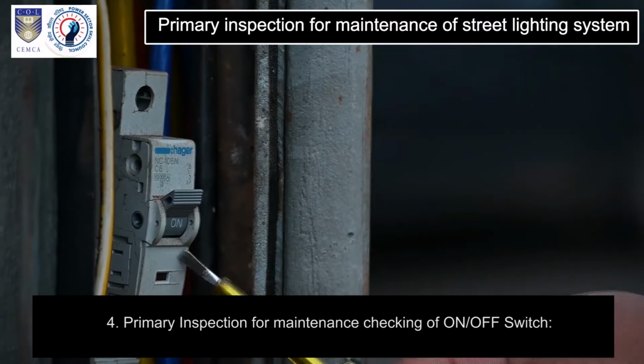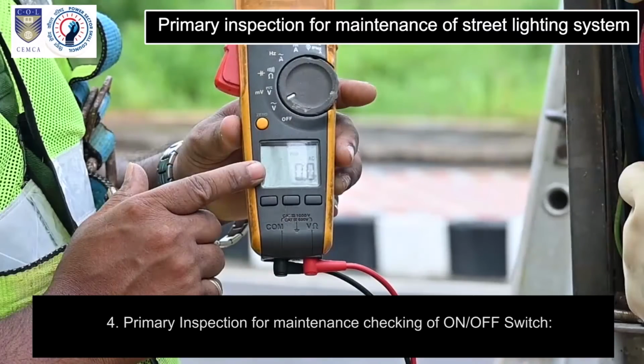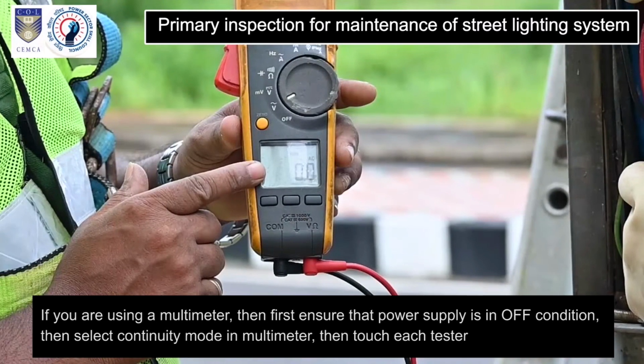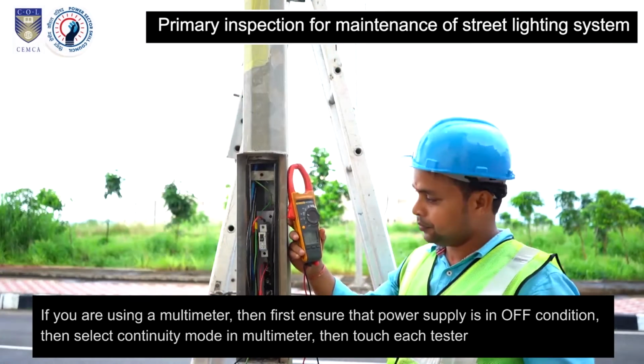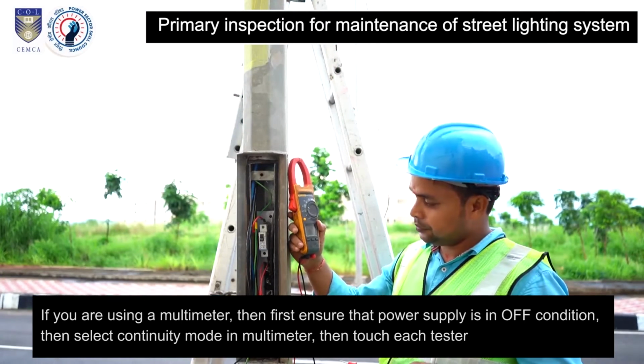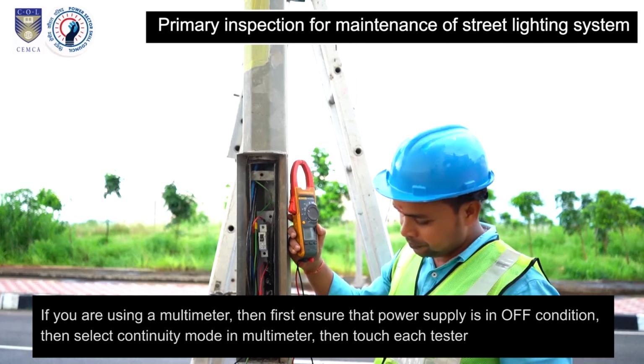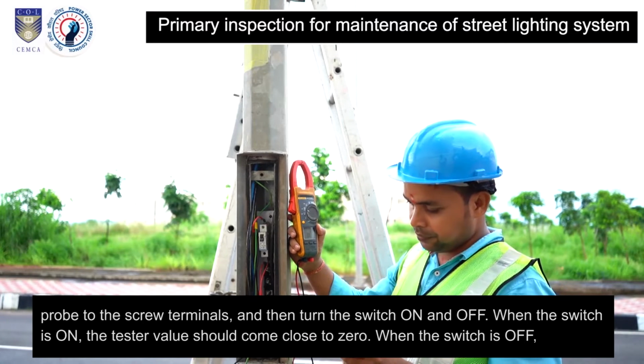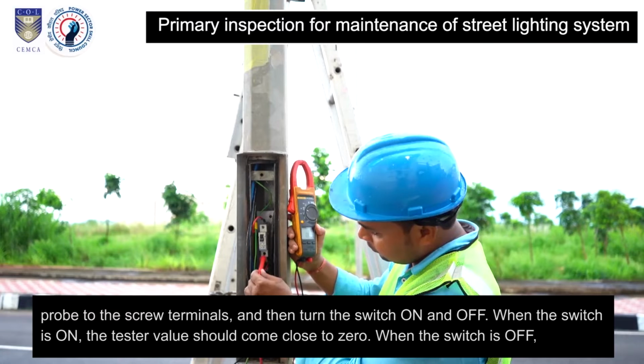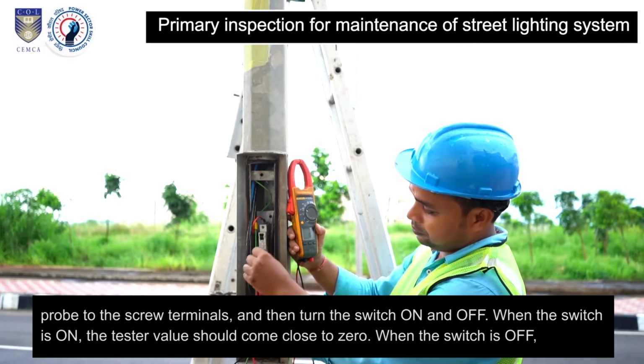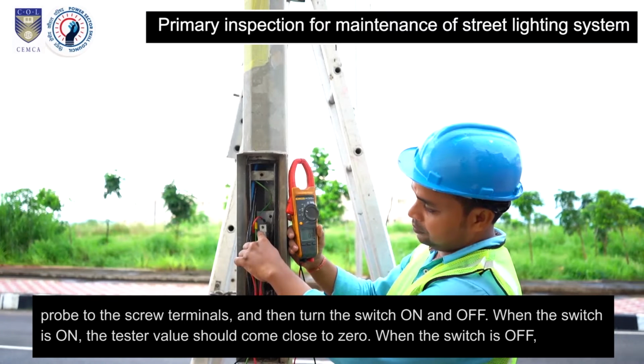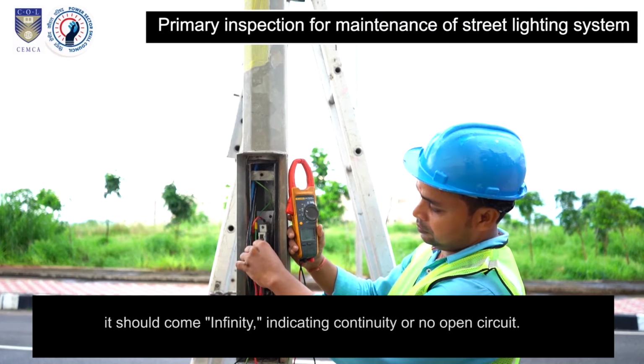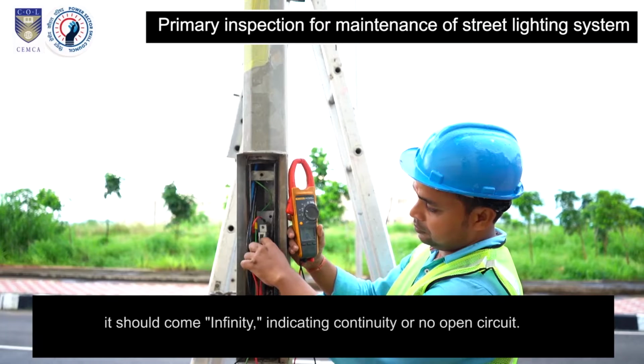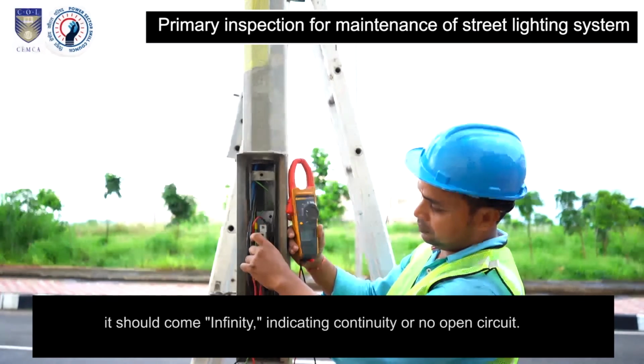4. Primary inspection for maintenance: checking of on or off switch. If you are using a multimeter, then first ensure that the power supply is in off condition. Then select continuity mode in the multimeter. Then touch each tester probe to the screw terminals and then turn the switch on and off. When the switch is on, the tester value should come close to 0. When the switch is off, it should come to infinity, indicating no continuity or open circuit.